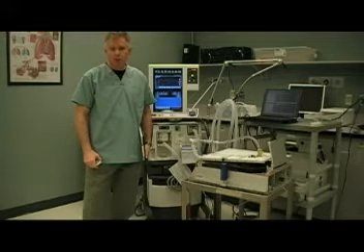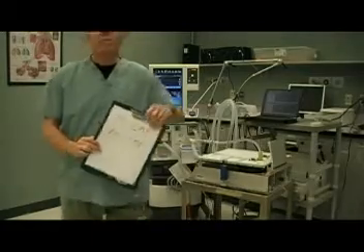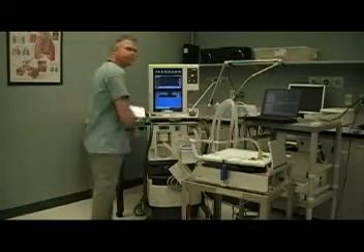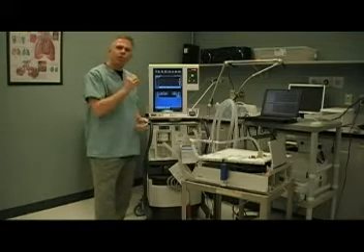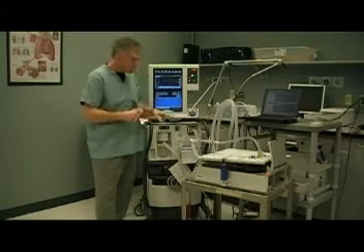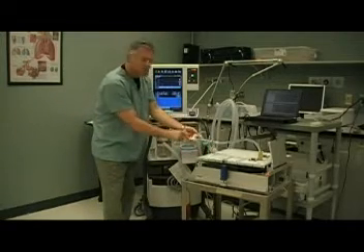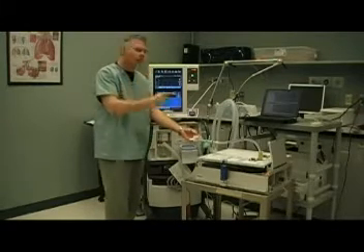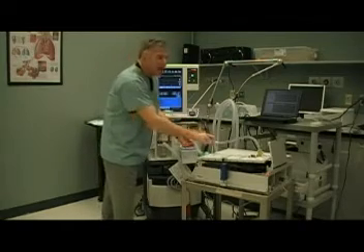We are talking about the mode of pressure control CMV and pressure control IMV. In pressure control continuous mandatory ventilation, we establish a set pressure that is delivered at the mouth. This pressure is held for a period of time until we get equalization between the ventilator mouth pressures and the lung pressures.